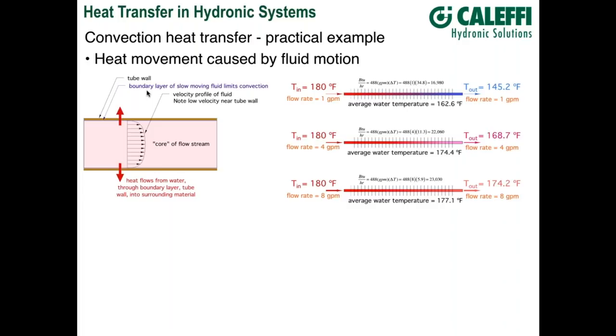Here's an example with fin tube. I took the same piece of fin tube with an inlet temperature of 180°F and a flow rate of 1 GPM, modeled a specific length of fin tube, and got an outlet temperature of 145°F. The average water temperature is 162.6°F, and we get a heat transfer rate of about 16,980 BTUs per hour.